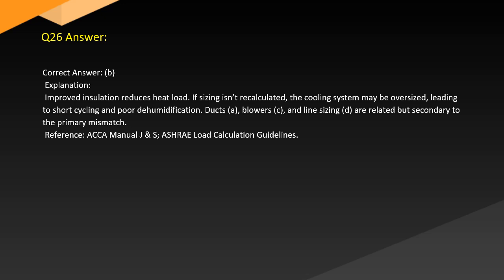Answer. Correct answer, B. Explanation. Improved insulation reduces heat load. If sizing isn't recalculated, the cooling system may be oversized, leading to short cycling and poor dehumidification. Ducts, A, blowers, C, and line sizing, D, are related but secondary to the primary mismatch. Reference: ACCA Manual J and S, ASHRAE Load Calculation Guidelines.